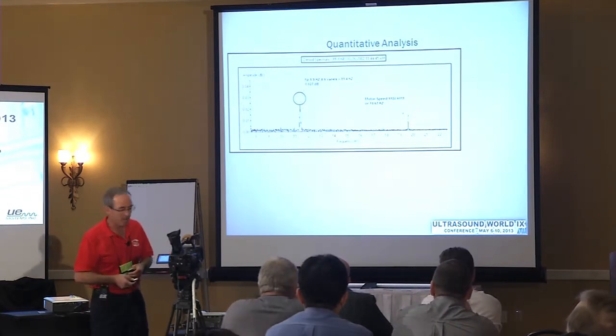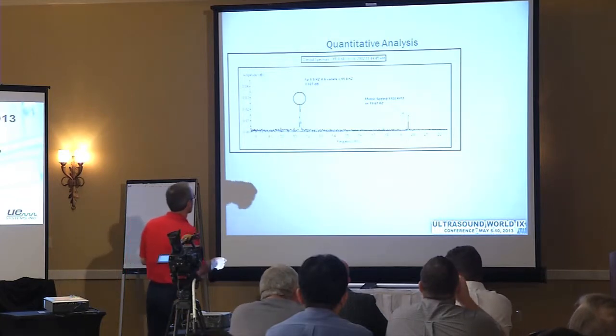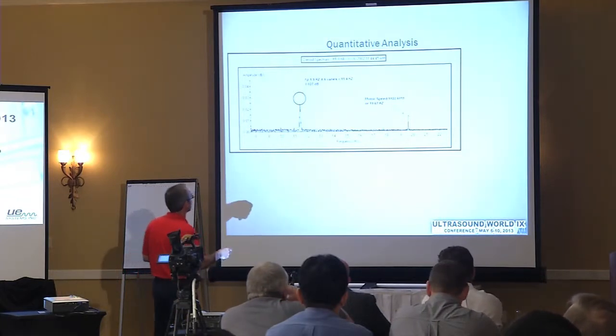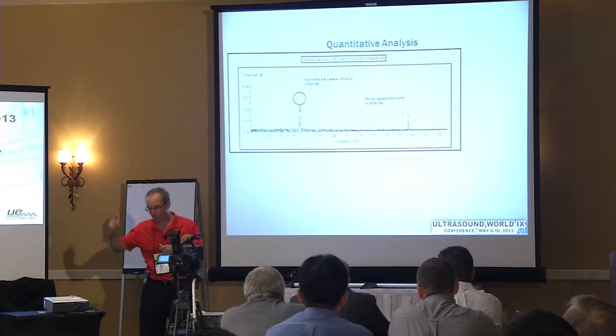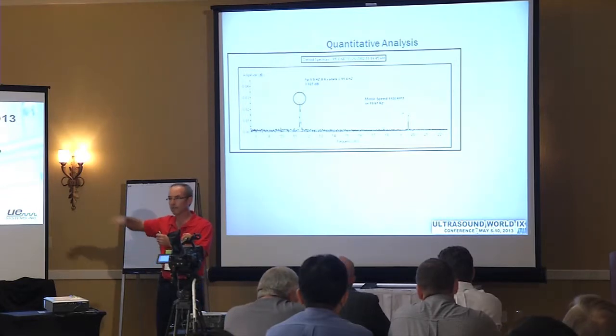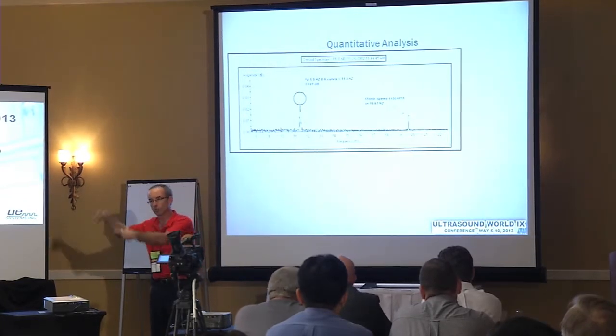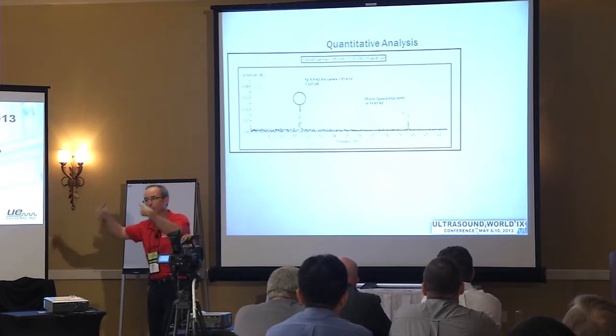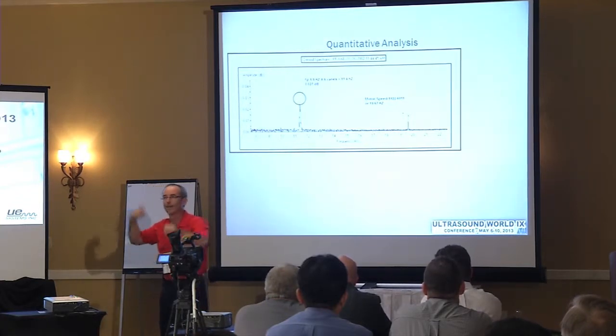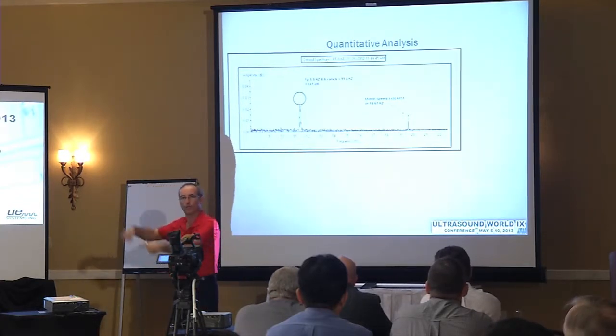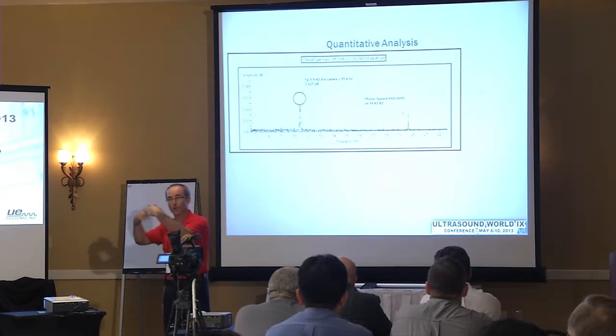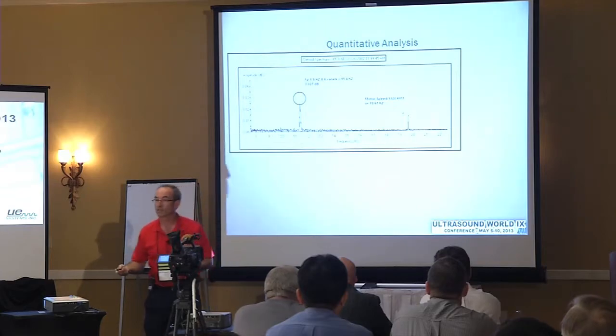If you're thinking about a pump vane, it's a pretty simple calculation. It's the pole pass frequency, which you've seen before - that's the stator winding, the rotating magnetic flux, and the rotor, which is slower. As these two invisible magnetic fields are turning, they pass each other, and every time they pass each other they create a flux. That's pole pass. Pole pass times the number of vanes is vane pass frequency, and that can be trended.